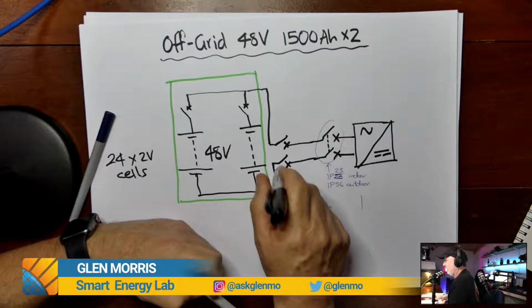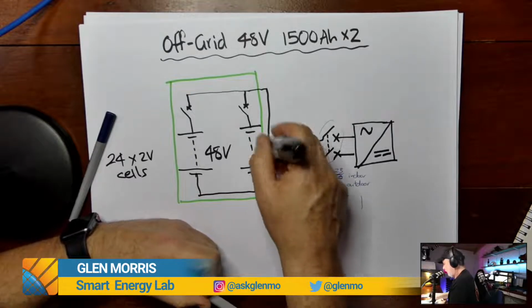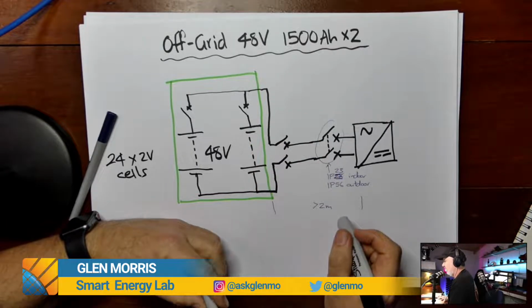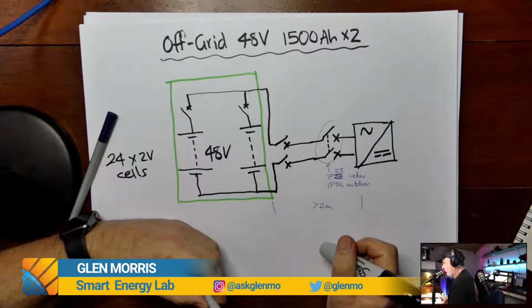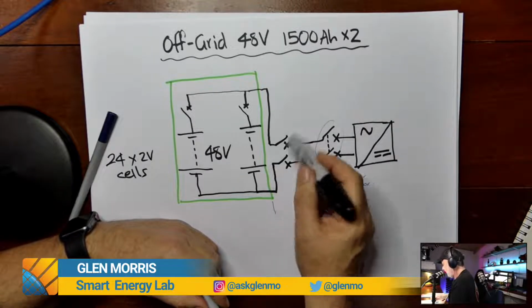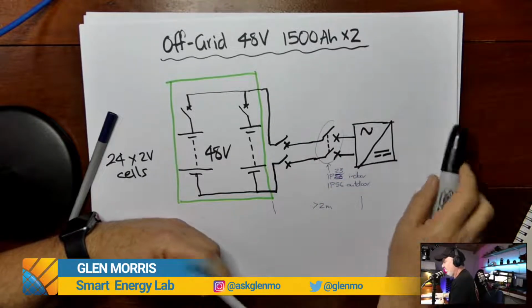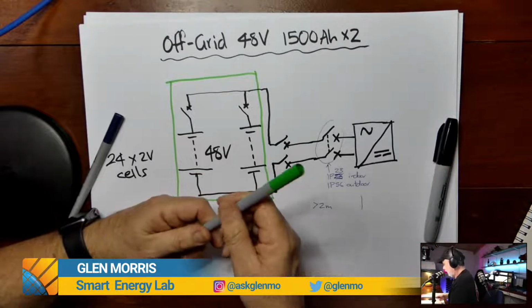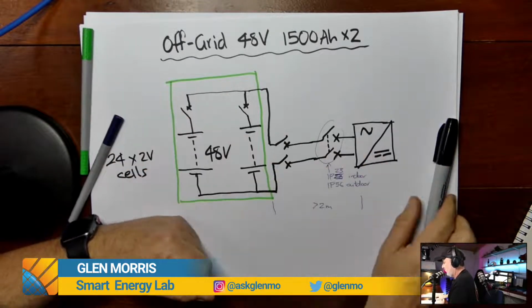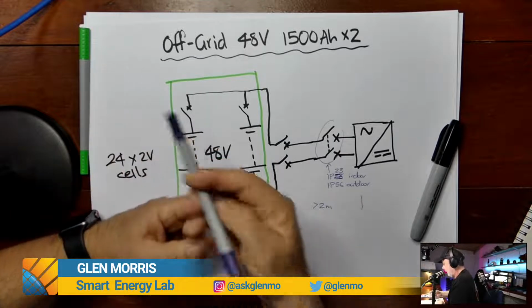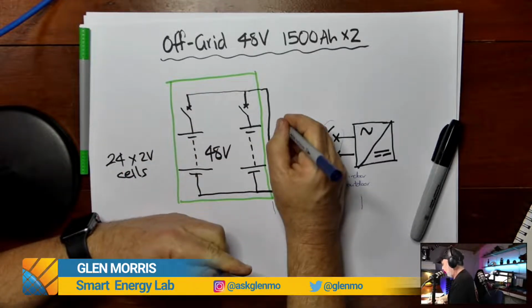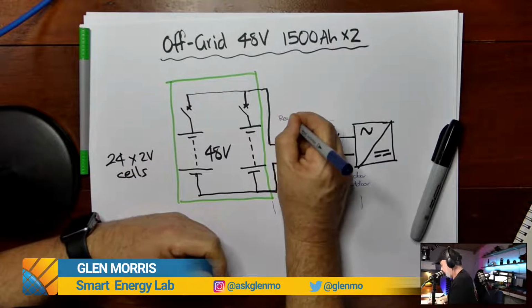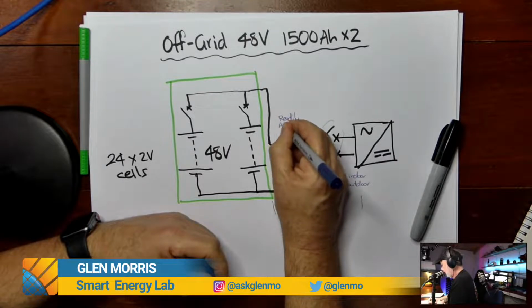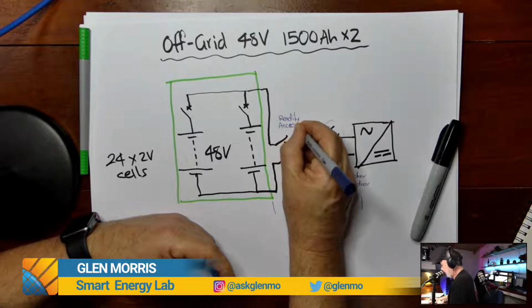Now, whether it's an overcurrent device depends on whether you've got a separate one. You might actually have overcurrent protection built into your battery system as well. But it needs to be isolation, and it needs to be readily accessible to the system operator. Now, that means that it can't require a tool. So this here, readily accessible, similar to a main switch.